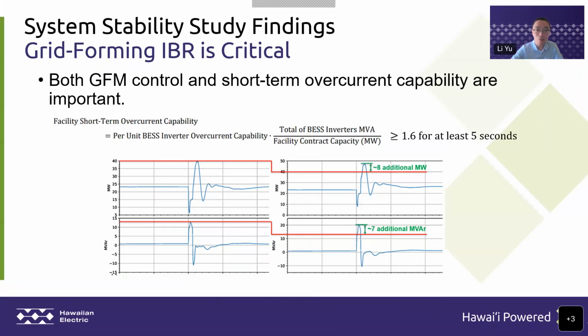So we require 1.6 per unit for battery inverters. This is only for the battery inverter, and for at least 5 seconds. Folks approached me during the general meeting asking if this also applies to wind or other technology. I would say, so far this is only for the battery inverter. We also looked at the bids received during the stage 1 and stage 2 projects. We already see many bids can reach this 1.6 per unit requirement. Next slide, please.